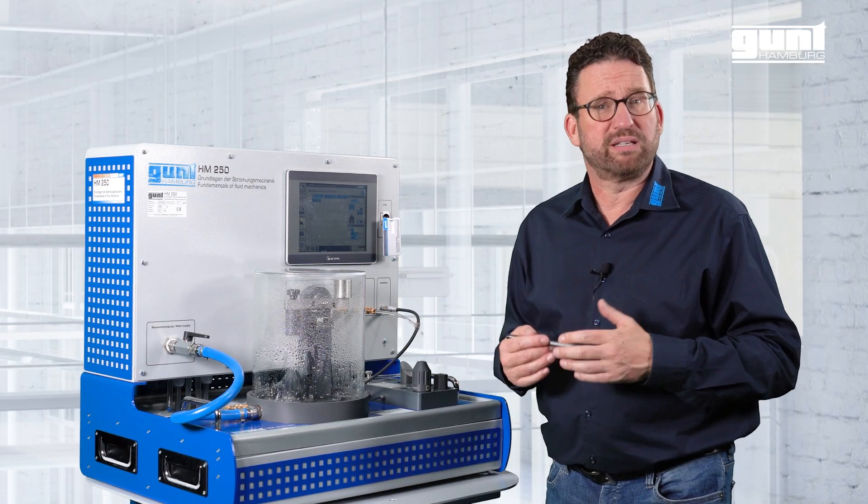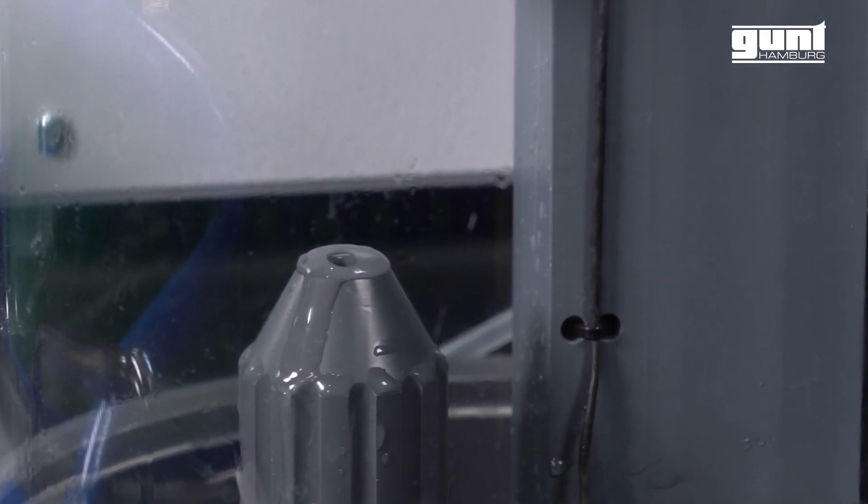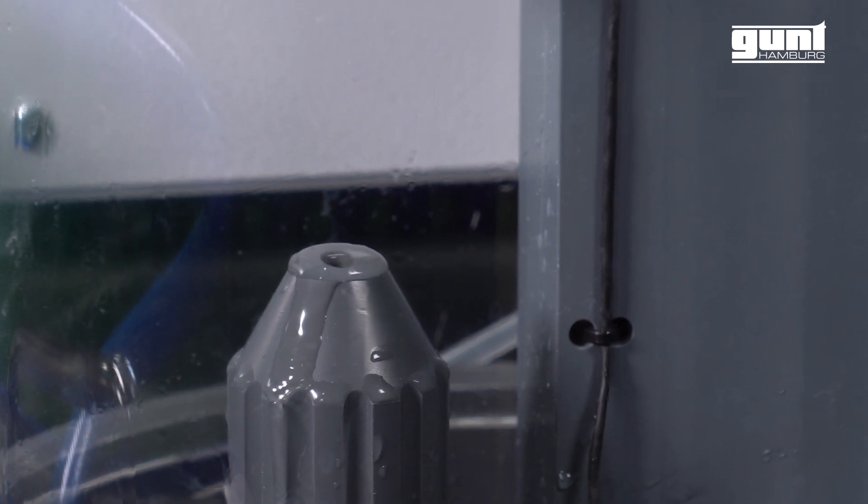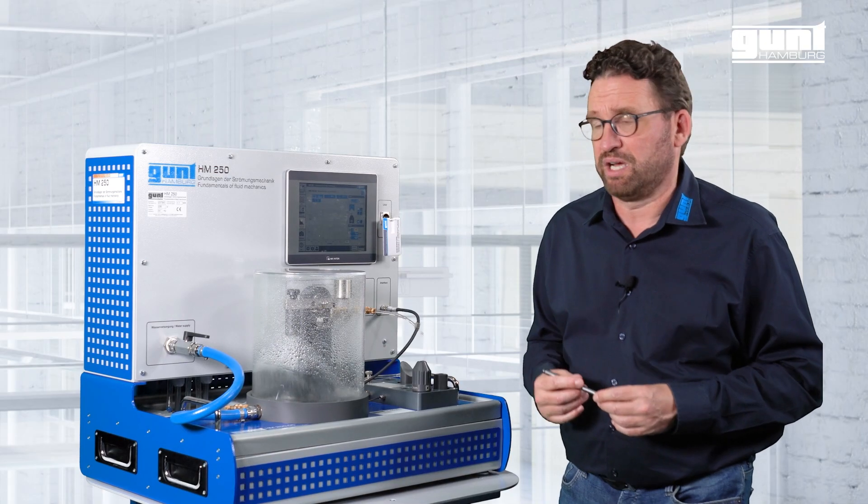Even though we have bled the system in the previous step I would still like to run the pump at a hundred percent capacity for a couple of seconds just to remove any air bubbles which may have formed in the system in the mean time.